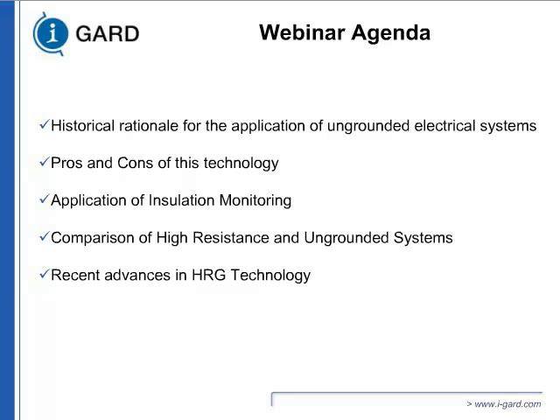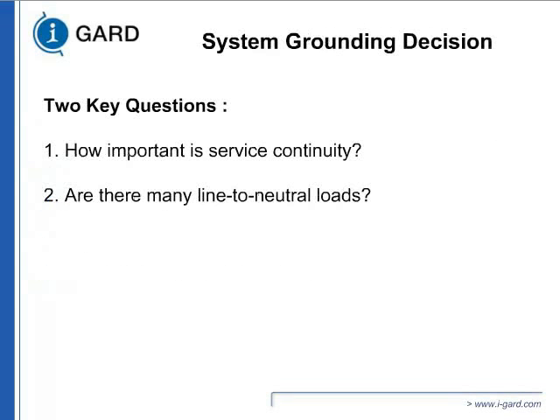So as we go along, you'll see that we are going item by item. First thing when you design the system grounding decision you have to make, first thing you ask yourself, how important is my service continuity? If power fails, what can happen? Do I create an unsafe condition? Do I create an environmental impact? Then you have to ask, or we used to ask before, are there any line to neutral loads? Because that will decide what you're going to do. Okay?